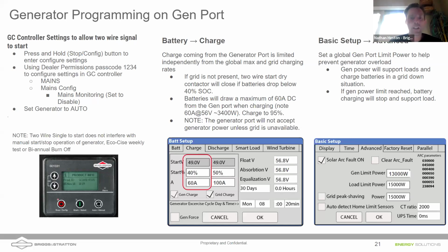Yeah, sure. What we're looking at here is a Sol-Ark 15K screen that's being shown to be programmed to charge both off of a grid source or off of a generator source. And so in the event of a grid down situation, first to note is that when you're programming the Solarc to charge the batteries off of both, it will prioritize grid first. So that means it will not start up the generator if grid is there. It'll wait to get to that value to use the grid source as an AC charging source.